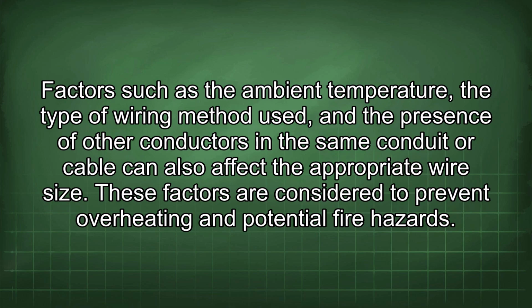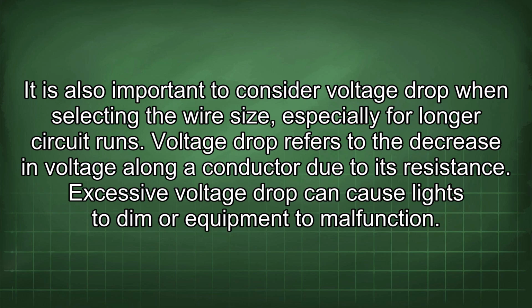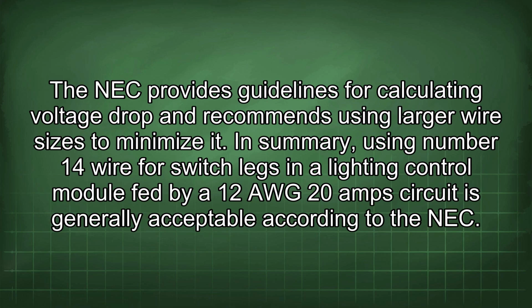Factors such as the ambient temperature, the type of wiring method used, and the presence of other conductors in the same conduit or cable can also affect the appropriate wire size. These factors are considered to prevent overheating and potential fire hazards. It is also important to consider voltage drop when selecting the wire size, especially for longer circuit runs. Voltage drop refers to the decrease in voltage along a conductor due to its resistance. Excessive voltage drop can cause lights to dim or equipment to malfunction. The NEC provides guidelines for calculating voltage drop and recommends using larger wire sizes to minimize it.